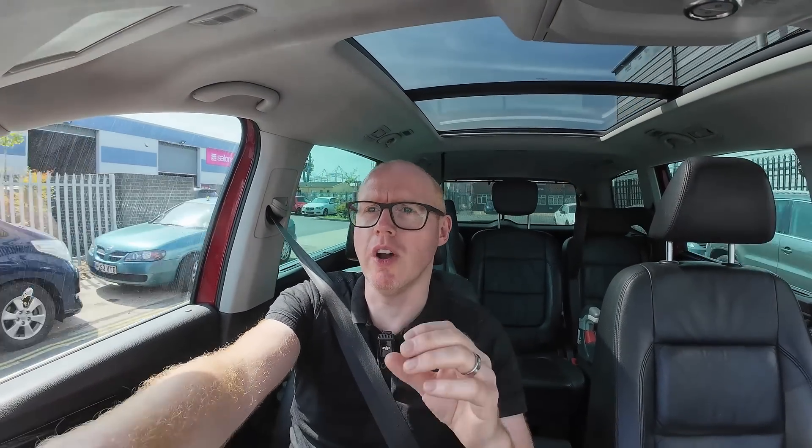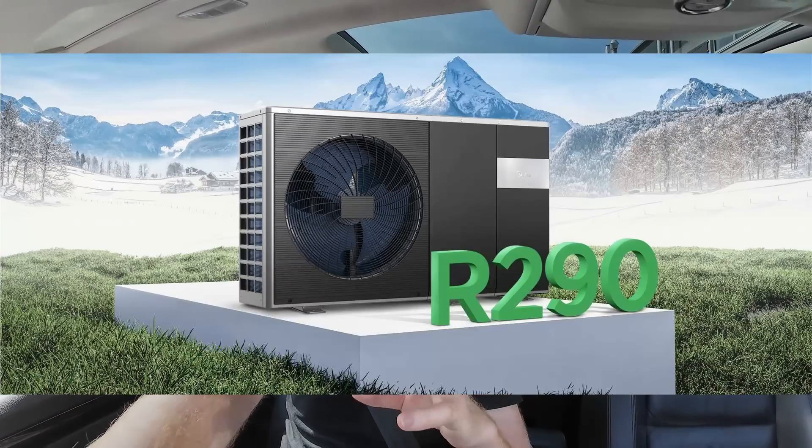Basically, when they're talking about high temperature heat pumps they're normally talking about heat pumps that use the refrigerant propane, which is R290. What that enables the heat pump to do is reach higher flow temperatures. From a technical perspective, that means you don't technically need to upgrade any of your radiators. You can also reheat your hot water cylinder without the assistance of any immersion heater — including, critically for some people, the Legionella cycle.